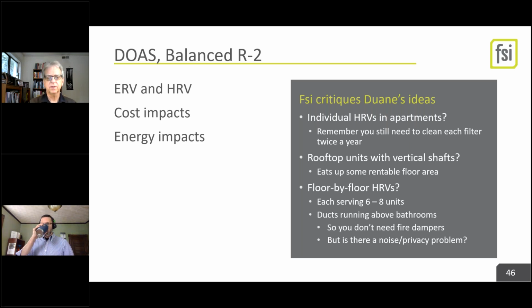Ben, there's another way to define the term bypass, and that would be that when there are correct outdoor temperature conditions, instead of running your air through the energy recovery, you'd just bypass it straight to the outside or your incoming air. Does that? Yeah. So those are those little dampers we were talking about, those teeny rectangles at the top and bottom of the core. The little units don't have them. Most residential units wouldn't have bypass dampers. And again, it's only a handful of hours a year where it would matter. They would remain closed almost every hour of the year. So if that's what they meant by bypass, it's not an official requirement for residential.